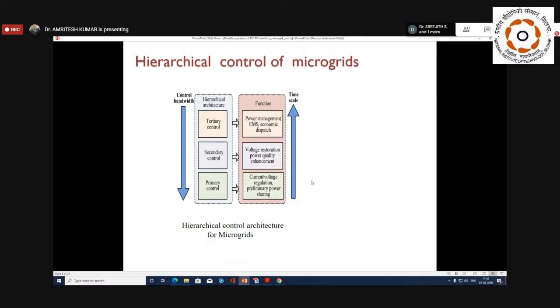Okay, so basically, secondary control will help ultimately to restore the voltage and enhance power quality. And tertiary control is basically used at the very top level for power management. Basically, in an area, there need not be only one microgrid, you can have different microgrids that are connected with the grid. So we require a master controller that will take care of the whole power that is being produced in the microgrid. So if a microgrid requires some power from the outside, or if there's excess power, it requires sending it to some other location, this tertiary control will take care of the overall power that is being circulated inside the microgrid. Okay, so in our discussion, I'm going to mostly focus on primary control, and thereafter we'll take over to the secondary control.